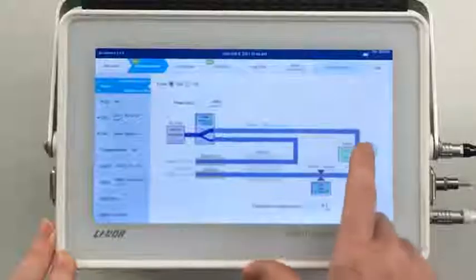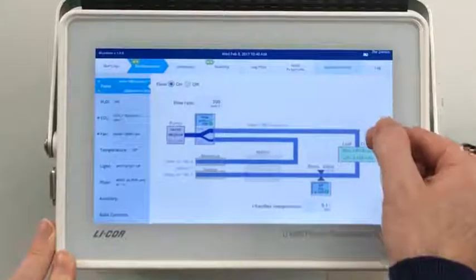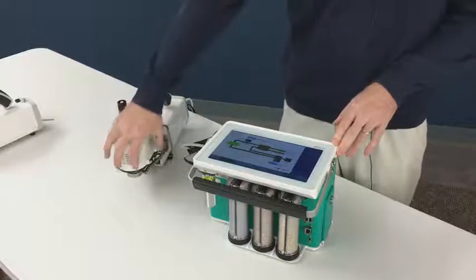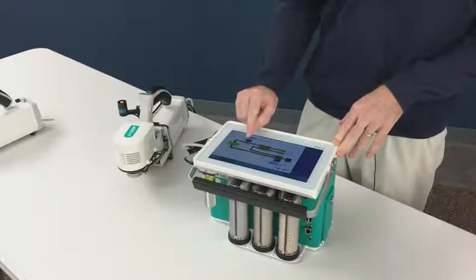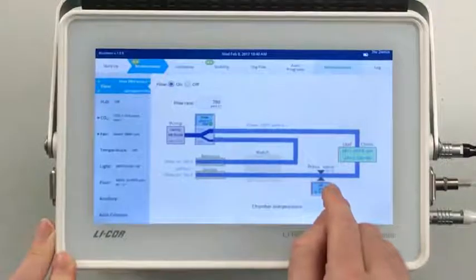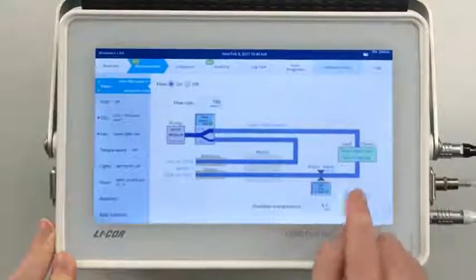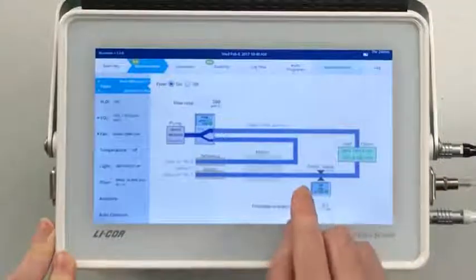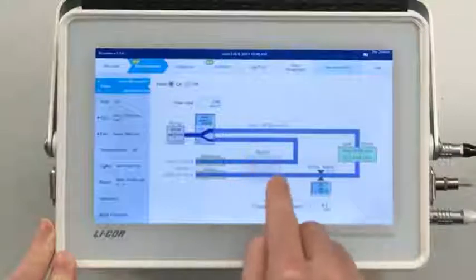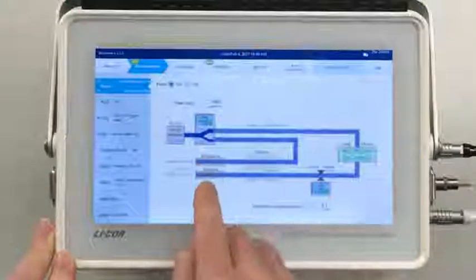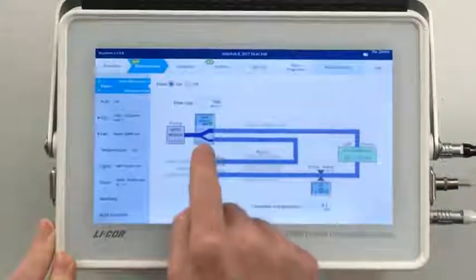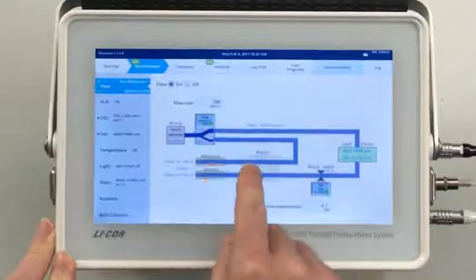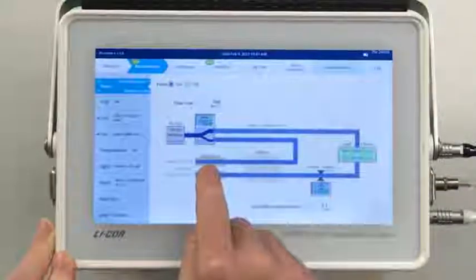And then I have two flow paths that come out. I have one that goes to my sample chamber. That's this part. It comes from the sample chamber through a user controllable valve to apply an overpressure inside the chamber. It comes from that valve to our match valve and then on to the sample and reference analyzers, right? So the reference path goes straight from the flow split through the match valve to the reference analyzer.